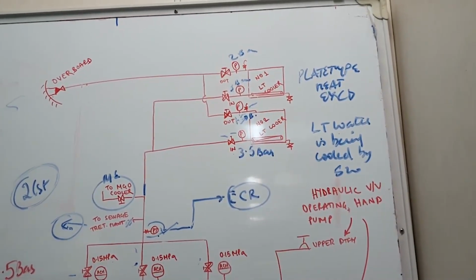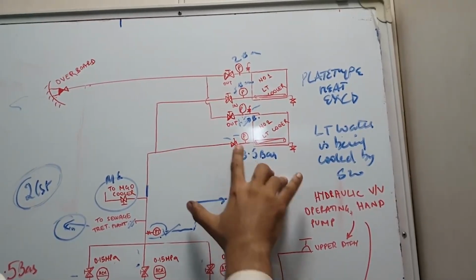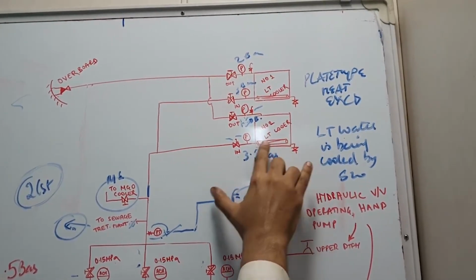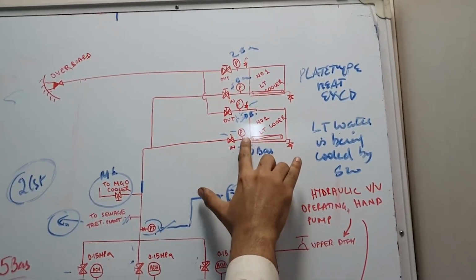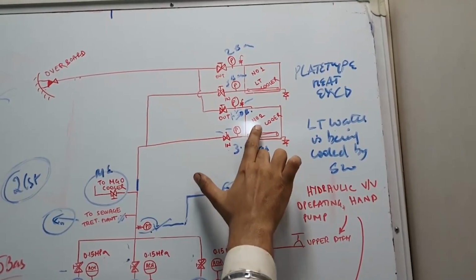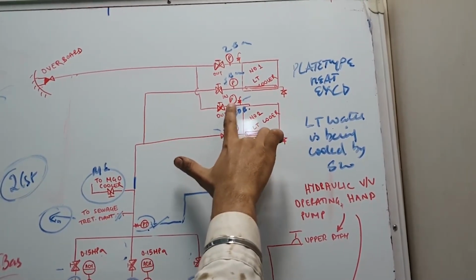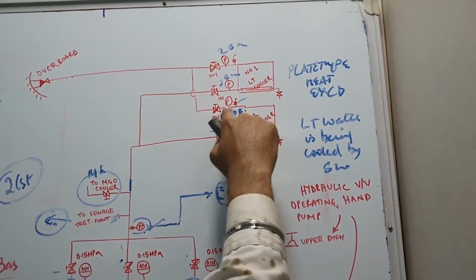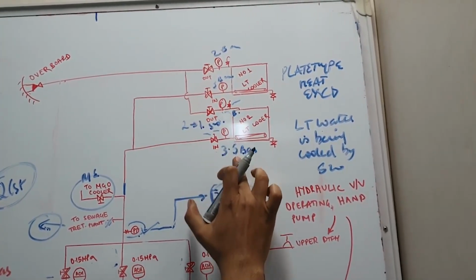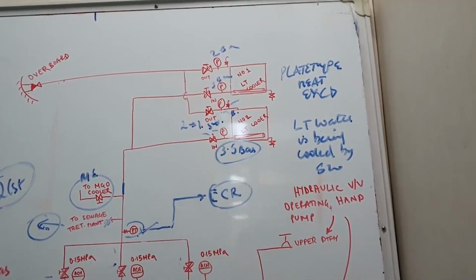Now guys, you see the inlet pressure is increasing. That means the water is not flowing in. What is the reason? Because your filter is getting choked over here, guys. So your filter, if it is getting choked, what will happen? It will not let the water go in easily. If water does not go through, then the outlet pressure is going to decrease from 2 bars to 1.5 bars, and also the inlet pressure is going to increase from 3 to 3.5 bars.